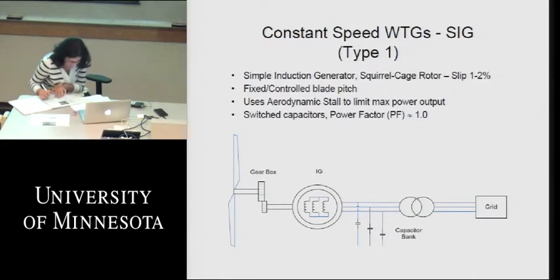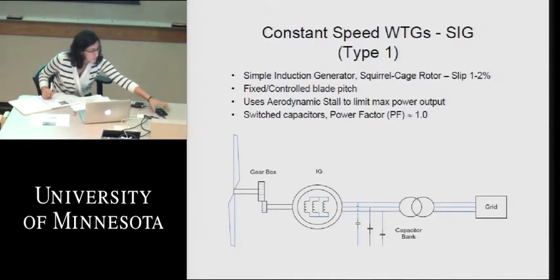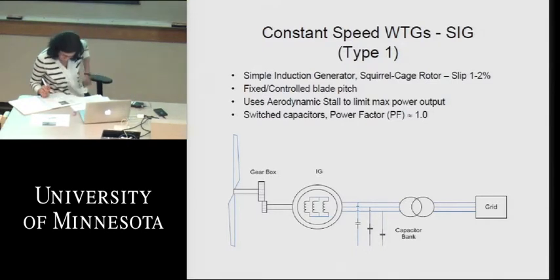these machines have fixed blades that do not pitch, we're counting on the aerodynamic law of stall to not overload this machine. The wind keeps coming stronger and stronger. There's a point when the aerodynamics of the blade start to produce turbulence on the backside of the blade, and hence you start increasing stall as the wind gets stronger and stronger. So that was the way to control overpowering a wind turbine up to about 15 years ago.